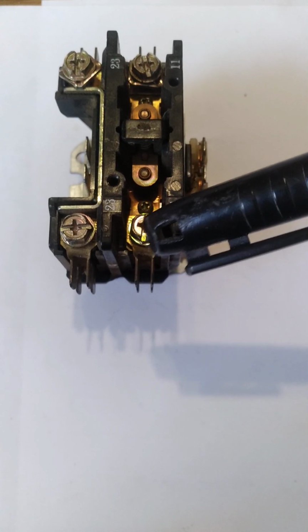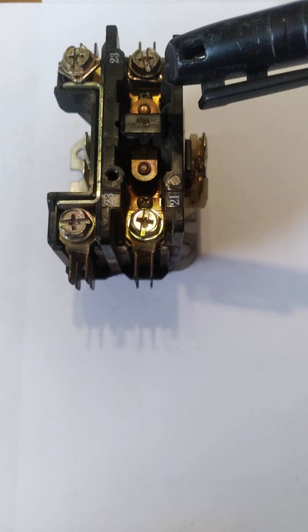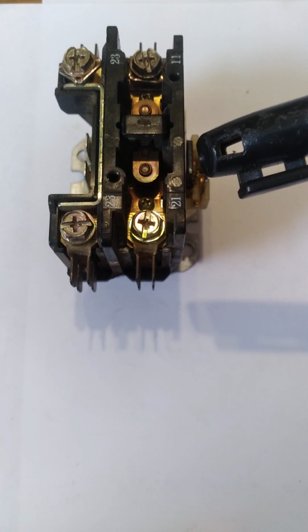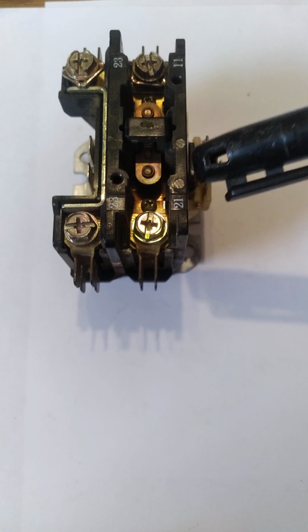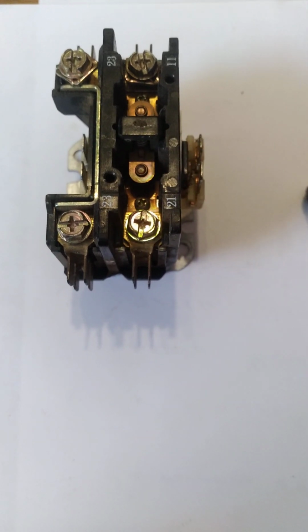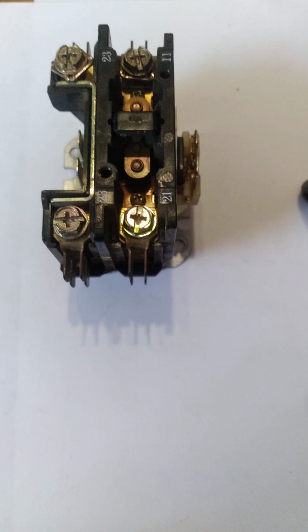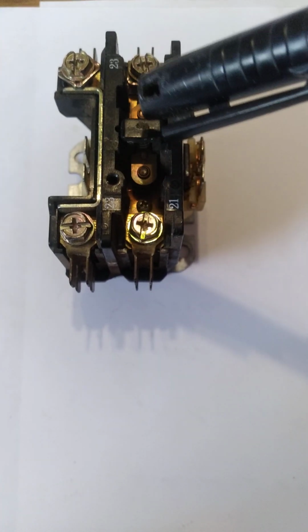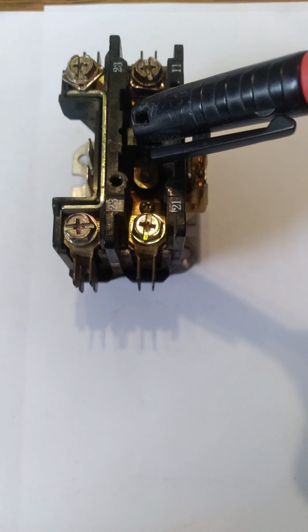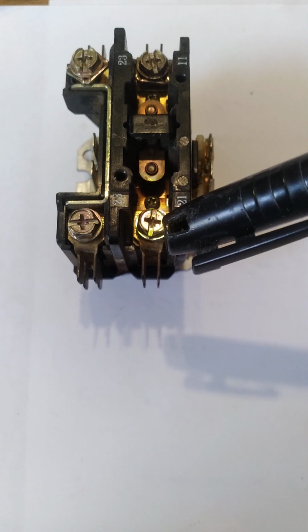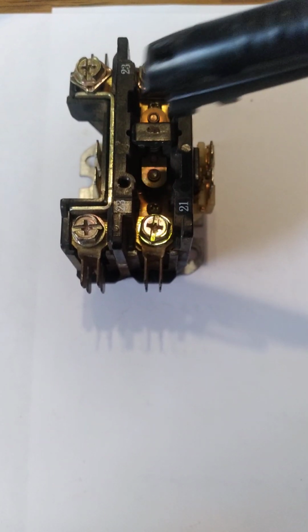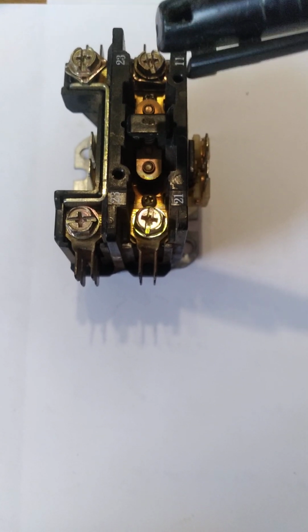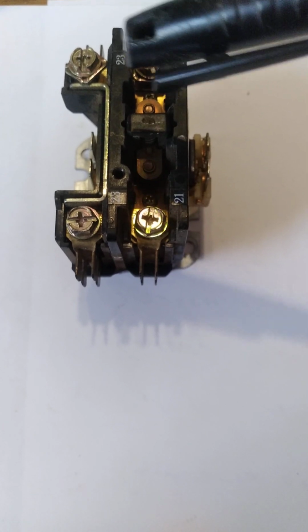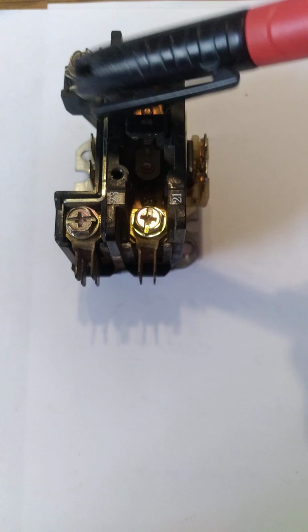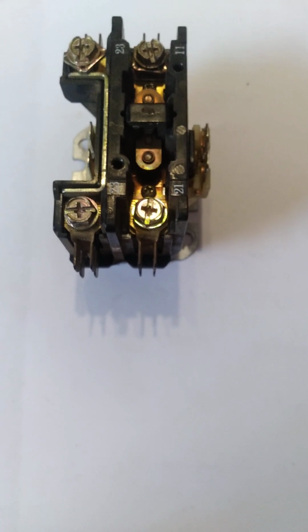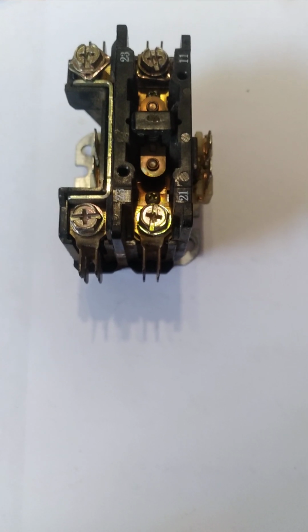So, how do we take this 240 volts and get to this side with 240 volts? Very simply, you have a coil that connects to this side and to this side. The coil is low voltage. Once the coil is energized, it creates a field and pulls this in. Hence, we're creating a contact. Now 240 goes from L1 to L2 to T1 to T2. And if one put their multimeter on this side, one should read 240, or this side to ground 120, this side to ground 120. Now we have enough voltage to run the compressor and the condenser fan motor.